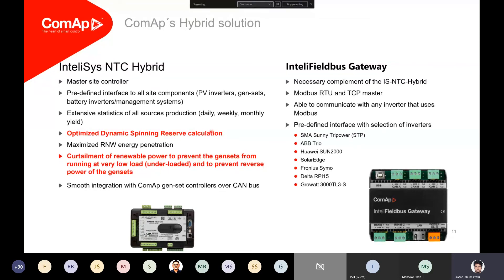It allows us to maximize overall penetration, schedule based upon load profiling — all of which we can program on our end. We also talk about curtailment: at a given point in time when you have very low load and you have oversized your PV or solar system, you want to protect your system from backfeeding to the generators or to the grid, unless you have net metering allowed. We communicate with the inverters to curtail this surplus power at any given point in time — all of that feature is incorporated in our hybrid microgrid controller.